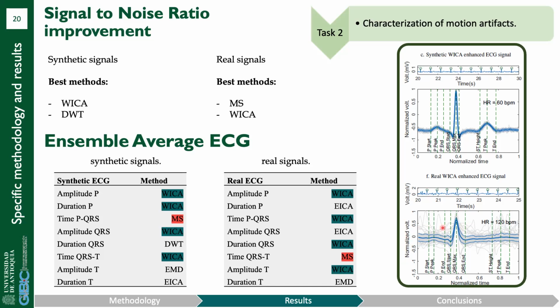But for example, I make the test of the signal acquired at rest at 60 beats per minute, 70 beats per minute, 80 beats per minute, in different heart rates, and comparing that the characteristics of the signal are in a similar position. Not the same, because as you mentioned, the dynamics of the ECG signal is very big, but at least in a similar position that we can ensure that the comparison is okay.